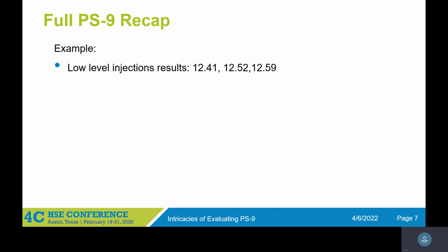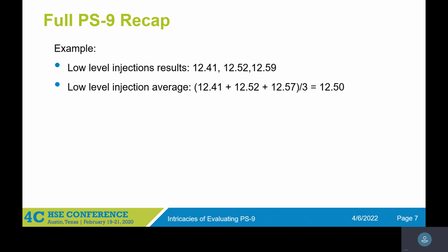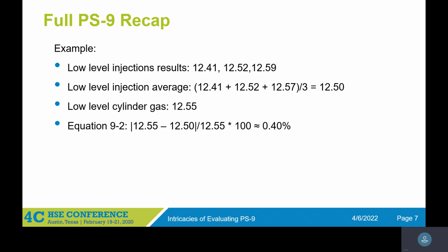So for an example, just to show you some numbers, we have low injection results. Say we have 12.41, 12.52, 12.59. We would then take each of those injection results and average them together out to 12.50. Then we look and see, what's our low level cylinder gas concentration? Well, say it's 12.55. Using equation 9-2 specified within Performance Specification 9, we take the absolute value of the cylinder gas concentration minus the injection average, divided by that cylinder concentration. So using the cylinder concentration as our point of reference, and then multiplying that out by 100, we're pretty close, within 0.4%, which is well within tolerances for these requirements.